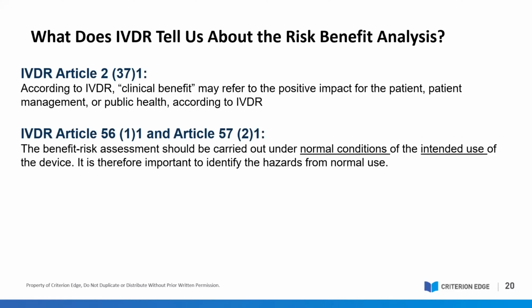There are regulations within IVDR that state that the overall residual risks should be compared against the benefits of the device to evaluate whether a high risk but highly beneficial device should be marketed.